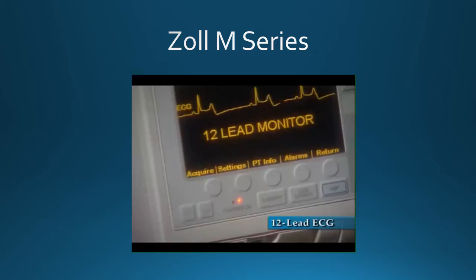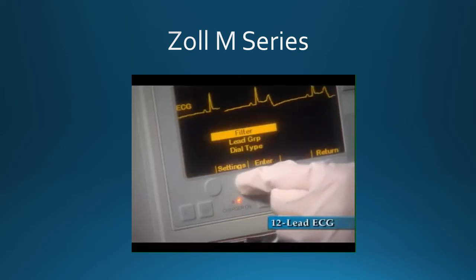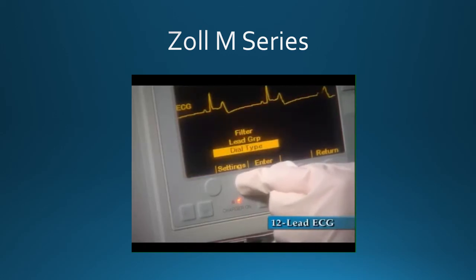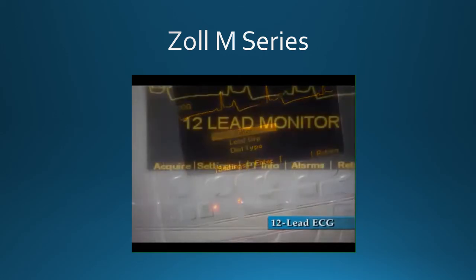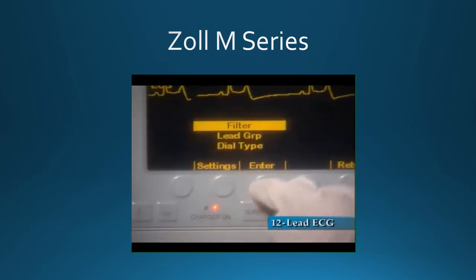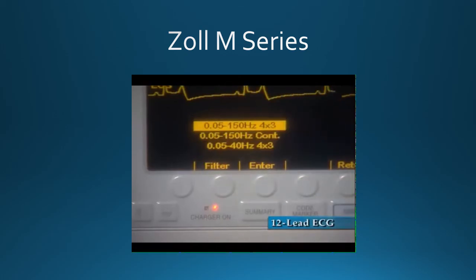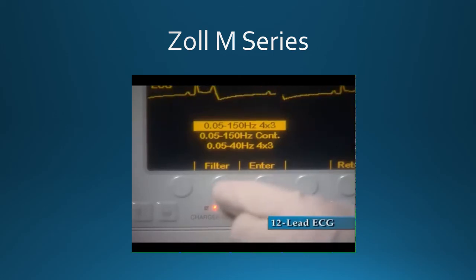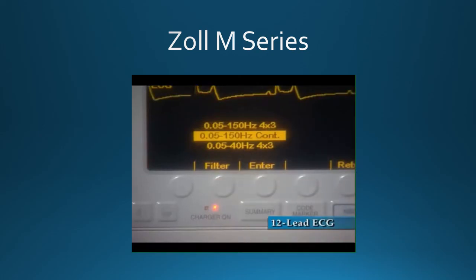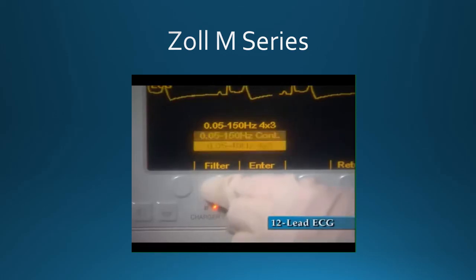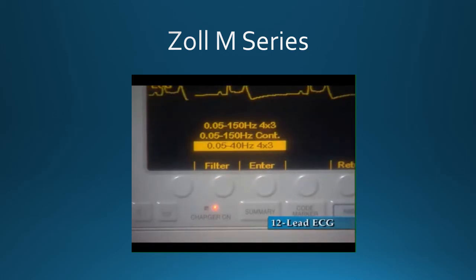The Settings soft key allows the user to change the ECG filter, lead group settings, or the dial type for telephone transmission. Selecting the Filter Settings soft key allows the user to select among the following 3 settings for 12-lead monitoring: 0.05 to 150 Hz for monitoring 12 leads in a diagnostic bandwidth, 0.05 to 150 Hz for continuous printout, 0.05 to 40 Hz for monitoring 12 lead when excessive artifact is present. This setting may also be used to acquire a 12-lead ECG under difficult conditions.